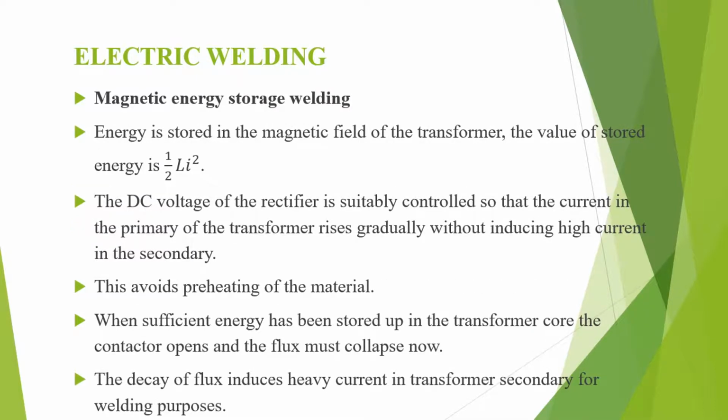Magnetic energy storage welding. The energy is stored in the magnetic field of the transformer, the value of the stored energy being half L i square. The DC voltage of the rectifier is suitably controlled so that current in the primary of the transformer rises gradually without inducing high current in the secondary. This will avoid preheating of the material.